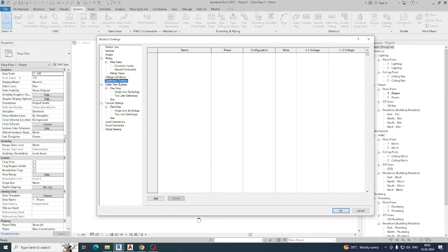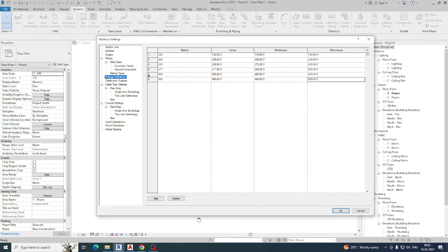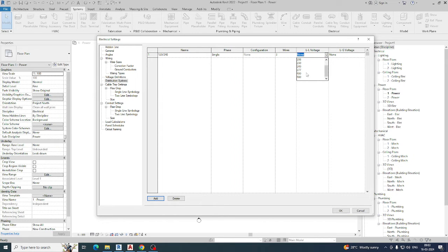Once you have set up the voltage definitions, go to the Distribution System. You need to add all the distribution systems here. The first one is 120/240 — add it as single phase. You can choose the phase from here. Wire size can be set to around 3. You can select 240 from here, but if 240 is not available, you need to add it — give the value 240, minimum as 230, and maximum as 260.